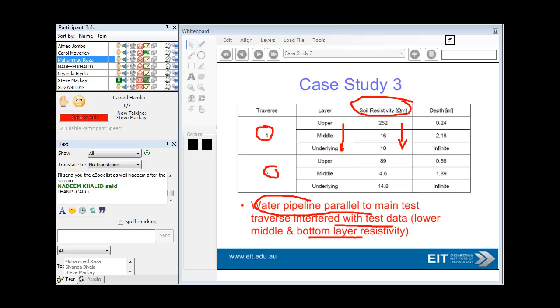Variations in soil resistivity are a source of uncertainty. You've got to look at the cost-effective solution, look at your site constraints, make use of other data such as your geotechnical information. And the other very important issue, which Rodney made a big point of, is to try and plot your measurements during the actual resistivity measurement process. Do not wait 3 hours till you go back to the office, otherwise you may see some kink in the data which you should have picked up then. Because going all the way back to the site could be 3 or 4 hours, maybe a day's travel, so try and do your measurements then and there.